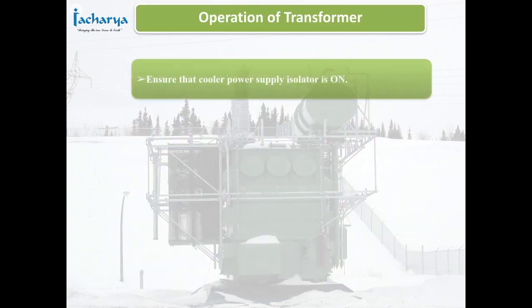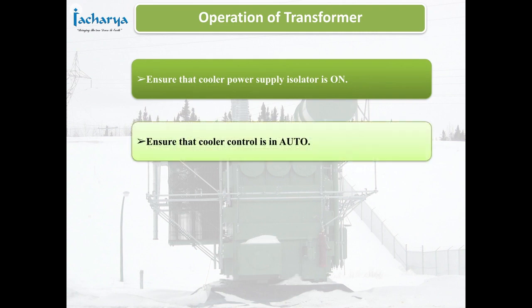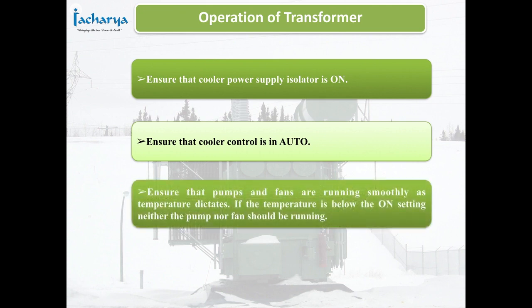Ensure that cooler power supply isolator is on. Ensure that cooler controller is in auto. Ensure that pumps and fans are running smoothly as temperature dictates. If the temperature is below the on setting, neither the pump nor fan should be running.